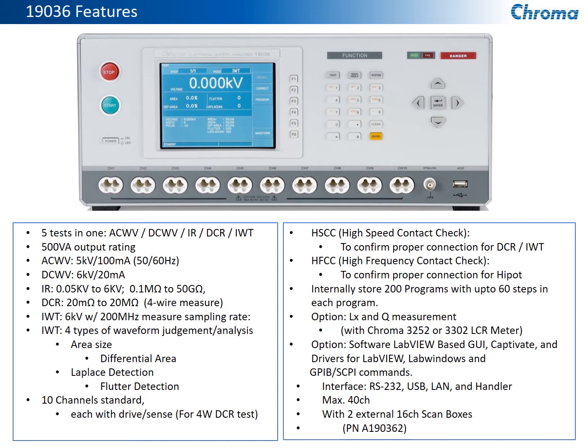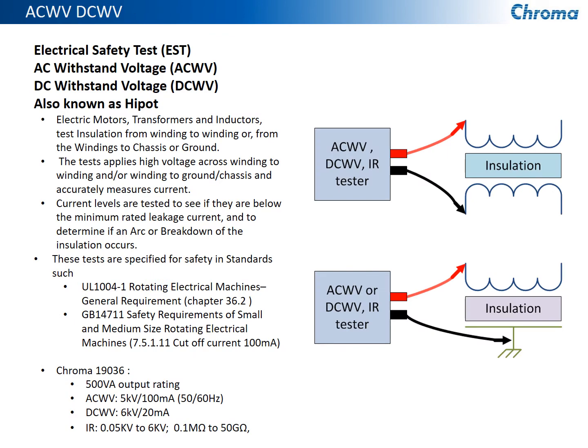So going on to the next level, I'd like to talk about AC withstand voltage and DC withstand voltage. That is a test that's been around for quite some time. It's referred to as a hipot test by most people. With this test on a transformer or on a motor stator, you'll normally measure winding to winding, trying to determine that the insulation between the windings is intact and meets some specified requirements. You can also measure between the winding and the housing on an electric motor, or any type of mechanical housing, metal housing around the device.